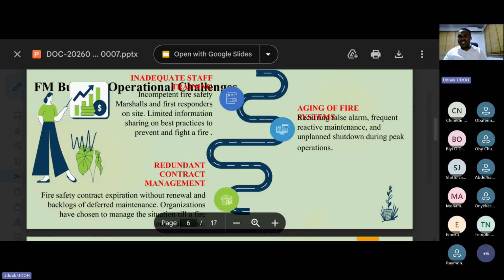At times you could just start hearing a false alarm. We've experienced that on site where the alarm keeps ringing until you go there and press reset, and the hydrant system keeps pumping because there's a leakage on one line that the jockey pump is having a signal from, and it keeps pumping, which it's not supposed to. It should only pump when the hydrant line is in use, but it's not in use. But because of limited experience with respect to inspection, the system fails, the flanges are bad. So there are all these little leakages always making the system fail.